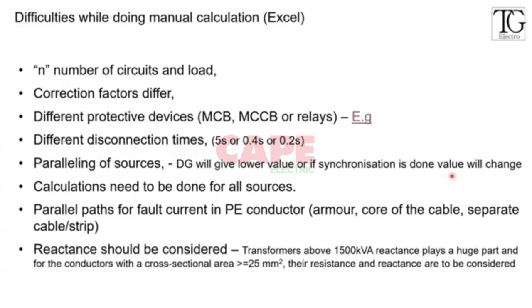And another problem you're going to have is the reactance. For the previous loop impedance value, I have not considered the reactance, because if I consider reactance also, it can increase the value by at most 10 to 20 percent. But if you're going to have transformers above 1500 kVA, reactance plays a huge part. And if you have conductors with cross-section above 25 square, reactance also plays a huge part in the total impedance of the circuit. So you should not ignore reactance.